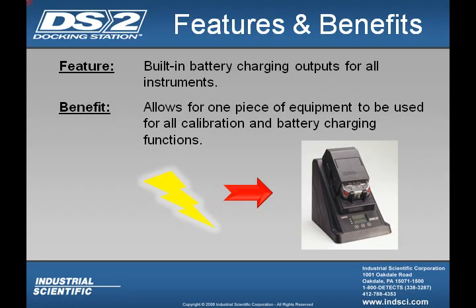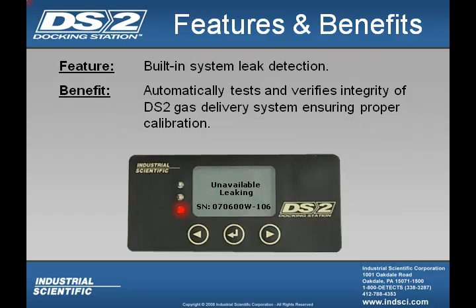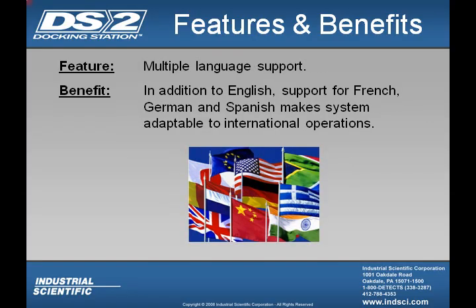And also your docking station has a built-in battery charger for all available instruments. And what this allows for is one piece of equipment to be used for not only calibration, but also for battery charging. And your DS2 has built-in system leak detection, and this automatically tests and verifies the integrity of the DS2 gas delivery system, ensuring proper calibration. And the last feature of the DS2 is multiple language support. In addition to English, support for French, German, and Spanish makes the system adaptable to international operations.